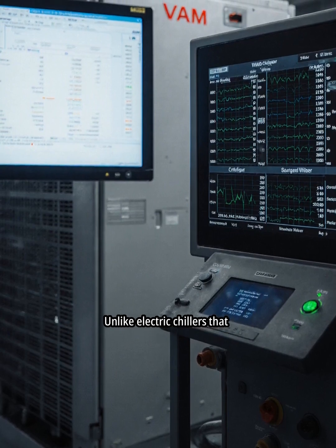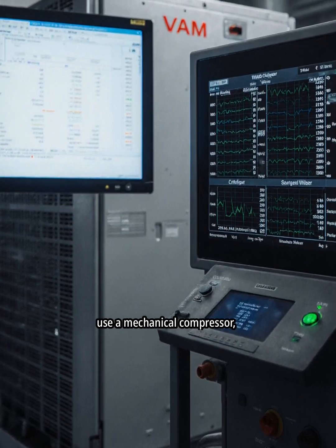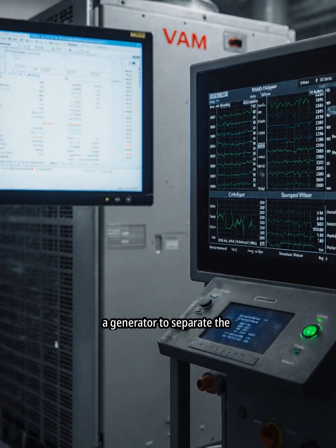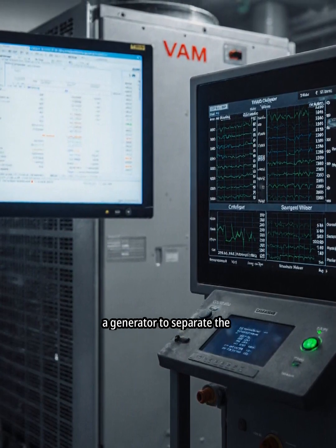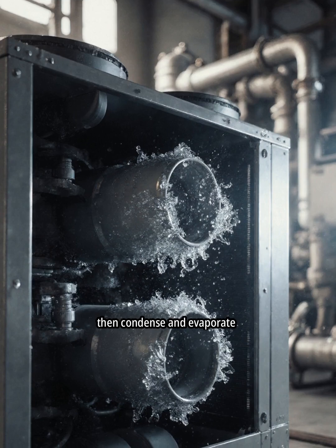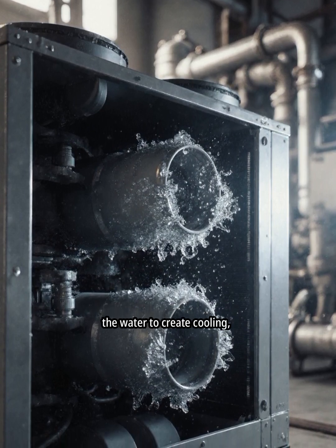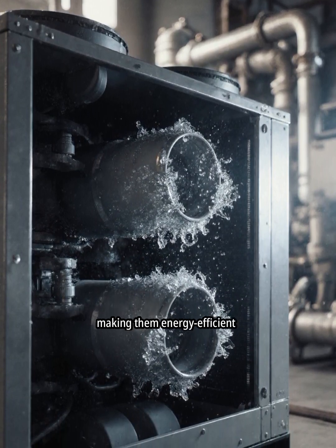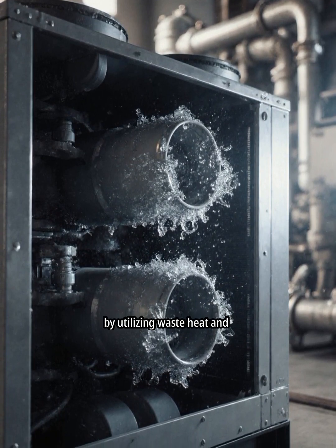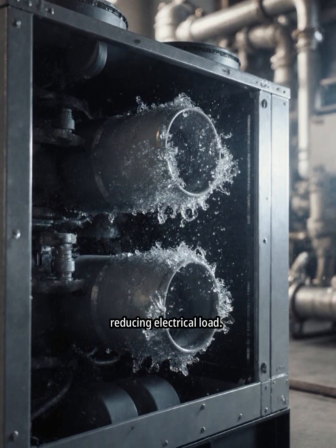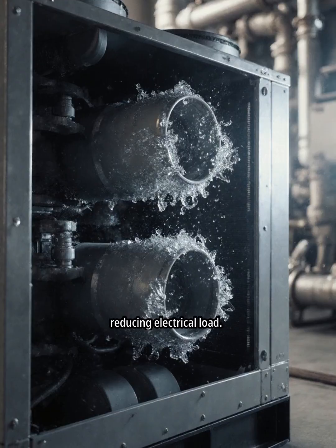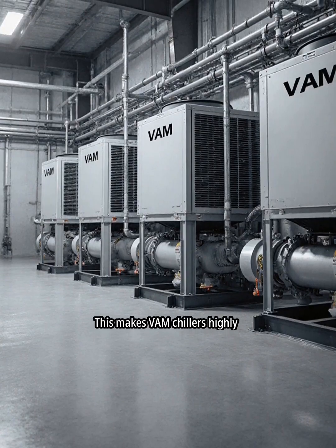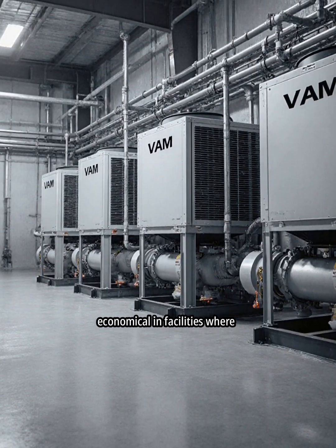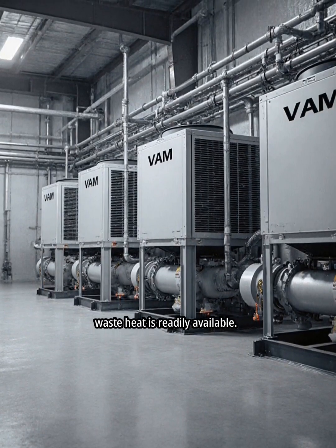Unlike electric chillers that use a mechanical compressor, VAMs use thermal energy in a generator to separate the water and absorbent, then condense and evaporate the water to create cooling, making them energy efficient by utilizing waste heat and reducing electrical load. This makes VAM chillers highly economical in facilities where waste heat is readily available.